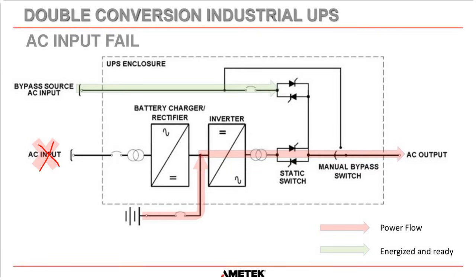If the AC input fails, the battery just continues supplying power to the inverter. And in truth, there is no switching involved here. It's just like you pulling the plug out the side of your laptop. Your laptop carries on going regardless. There's no switching. It doesn't switch to battery. The battery is in parallel with the charger. So once the charger goes off, the battery is just there. It just carries on going regardless. The inverter does not know that there is a difference in power between what's coming from the charger and what's coming from the battery. It just carries on regardless as normal.